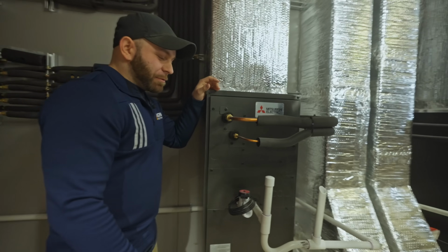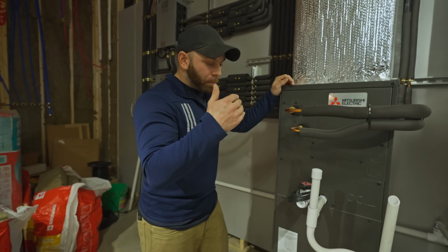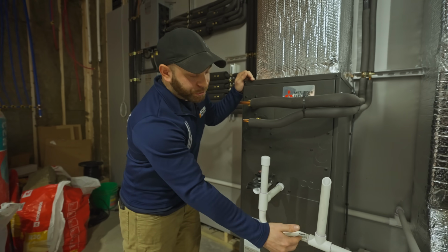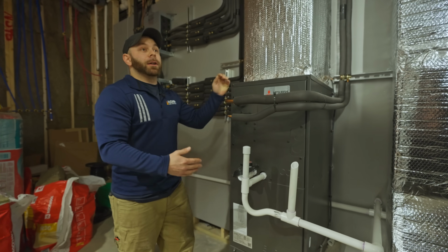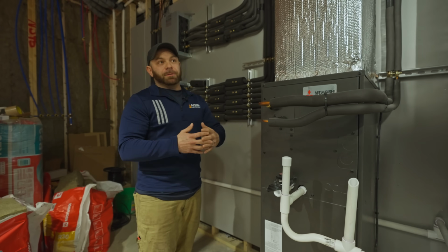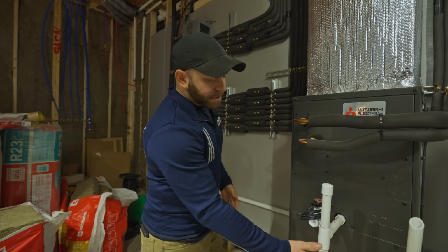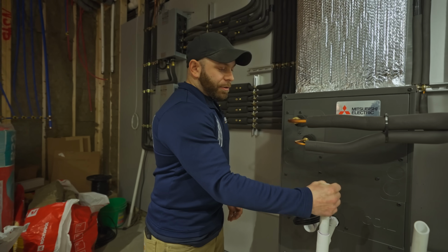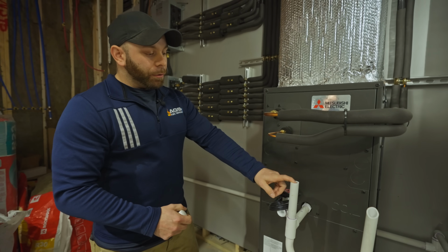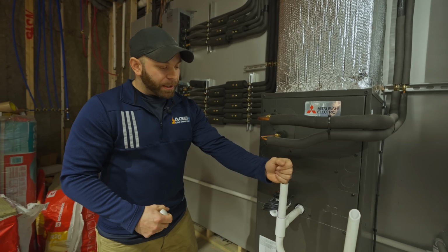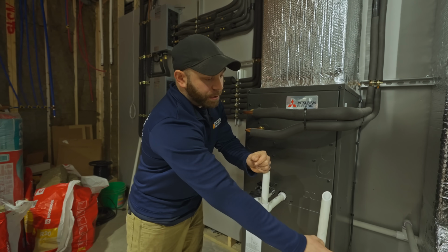Dry nitrogen is what we use to really push and clean these P-traps, because over time the P-trap will get built up with dust and debris that just sits there. So normally we put in what we call a clean out, so that it will blow out and clear the P-trap right after.